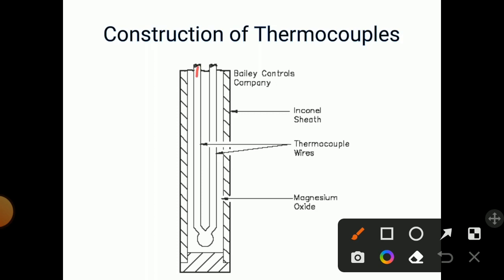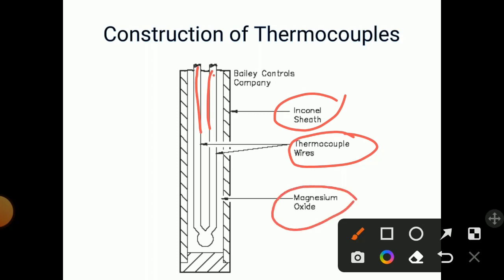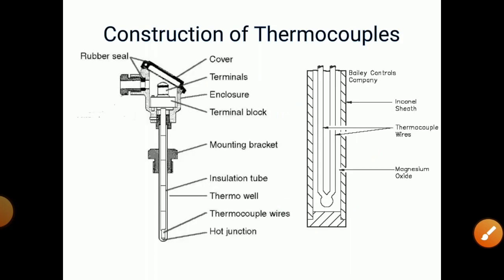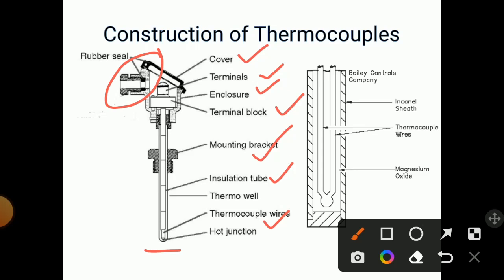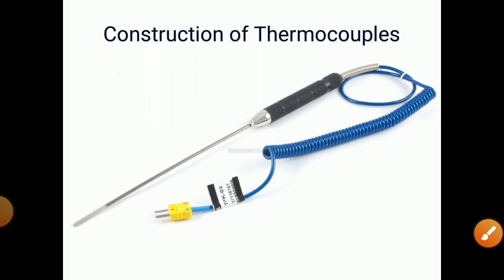The thermocouple wires are protected with an Inconel sheath on the outer side, and inside that, magnesium oxide is placed. Additional outer elements include a cover, terminals, enclosure, terminal block, mounting bracket, insulation tube, and below that the thermocouple wires, with the hot junction at the bottom sealed with a rubber seal. This is the construction of thermocouples — this is the actual thermocouple that can be obtained from the market.